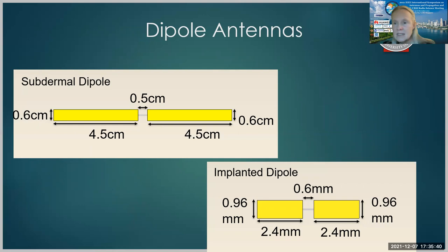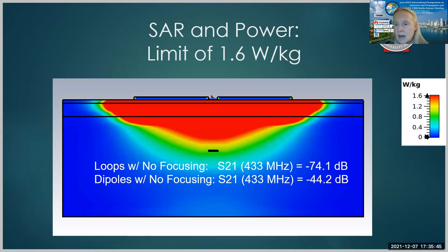So this is what happens with the SAR in this case. Notice that we've got a dipole antenna above and a dipole antenna below. And we end up with a very uniform SAR pattern actually here. So when we considered loops with no focusing, the S21 was minus 74 dB. The dipoles, on the other hand, with no focusing are better at minus 44 decibels. So already we're seeing a better transfer of power from a dipole on the outside to a dipole on the inside.